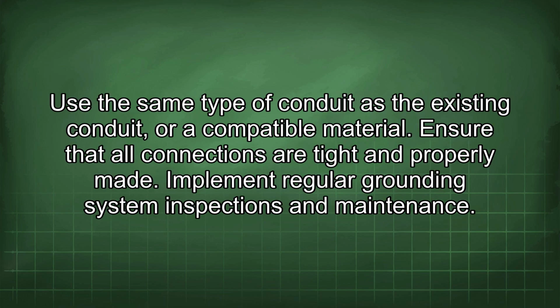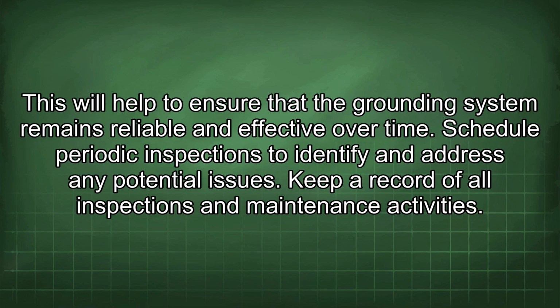Use the same type of conduit as the existing conduit or a compatible material. Ensure that all connections are tight and properly made. Implement regular grounding system inspections and maintenance. This will help to ensure that the grounding system remains reliable and effective over time. Schedule periodic inspections to identify and address any potential issues. Keep a record of all inspections and maintenance activities.